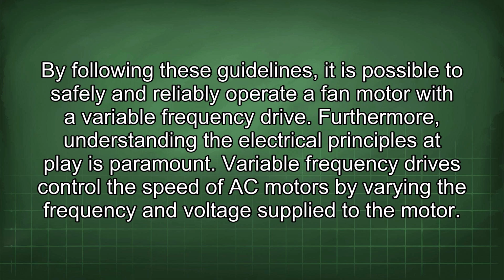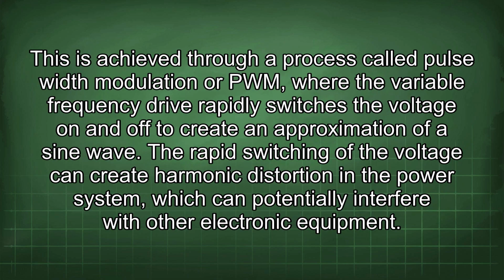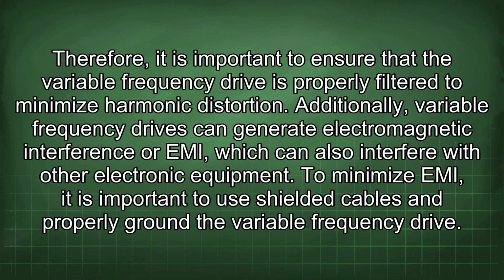Variable frequency drives control the speed of AC motors by varying the frequency and voltage supplied to the motor. This is achieved through a process called pulse width modulation, or PWM, where the variable frequency drive rapidly switches the voltage on and off to create an approximation of a sine wave. The rapid switching of the voltage can create harmonic distortion in the power system, which can potentially interfere with other electronic equipment. Therefore, it is important to ensure that the variable frequency drive is properly filtered to minimize harmonic distortion.